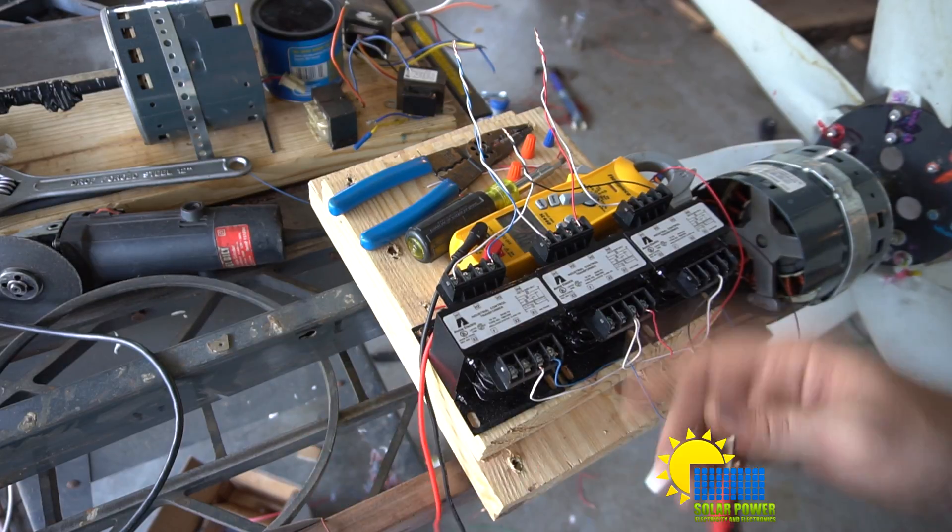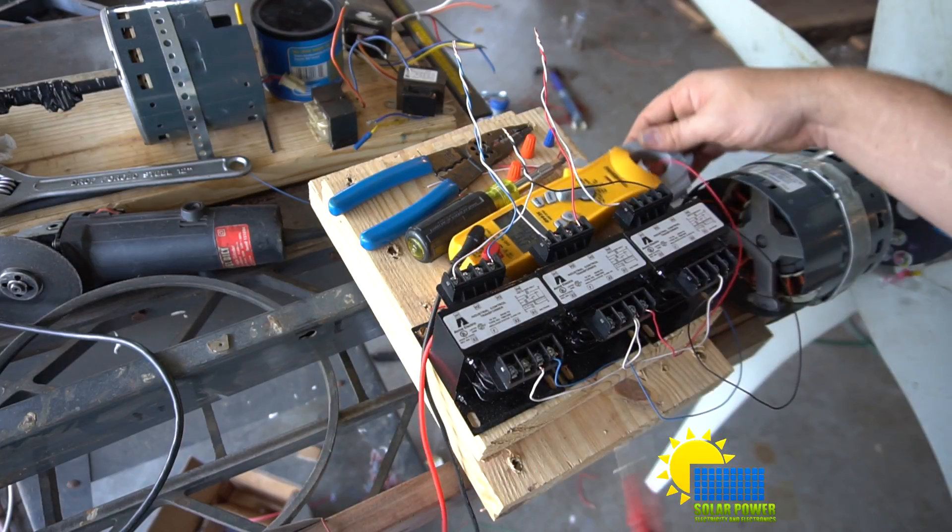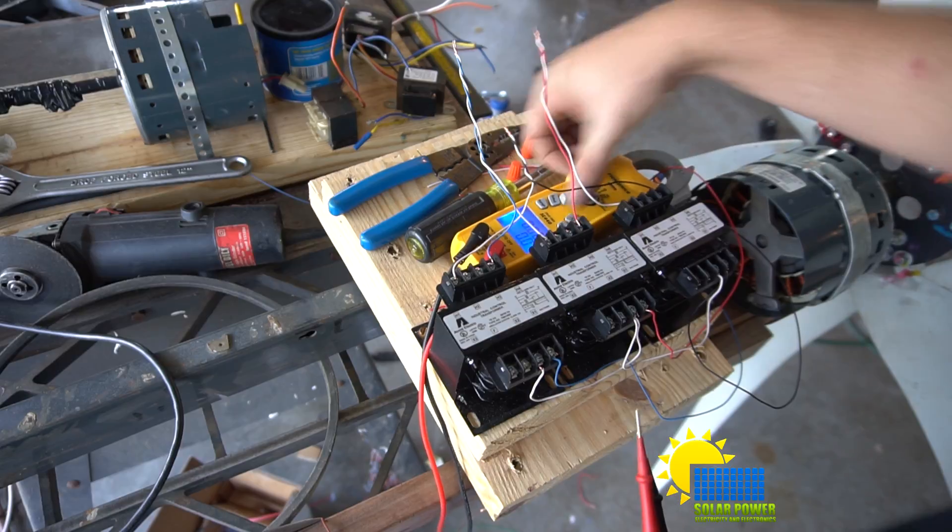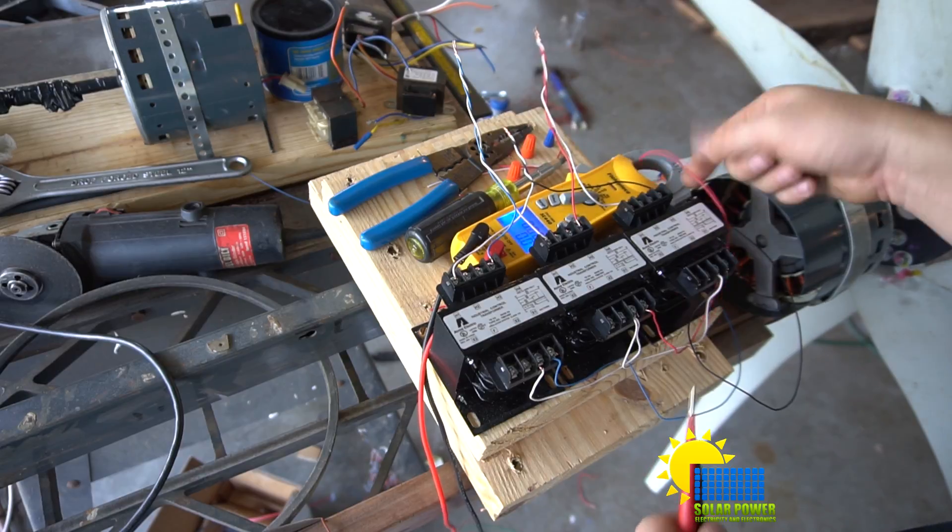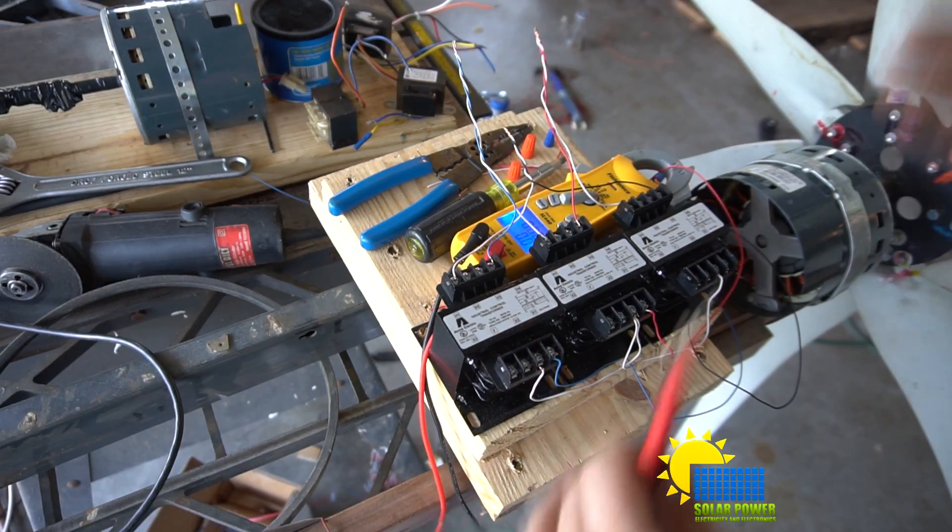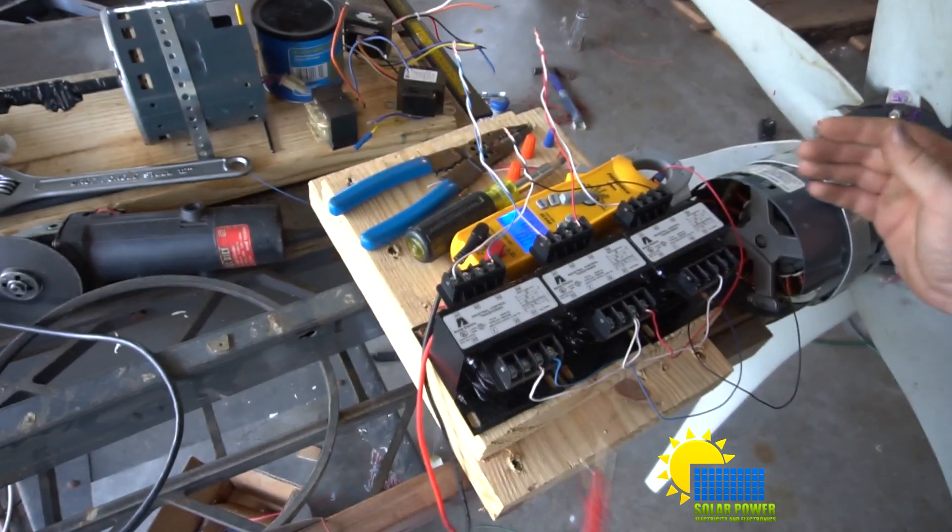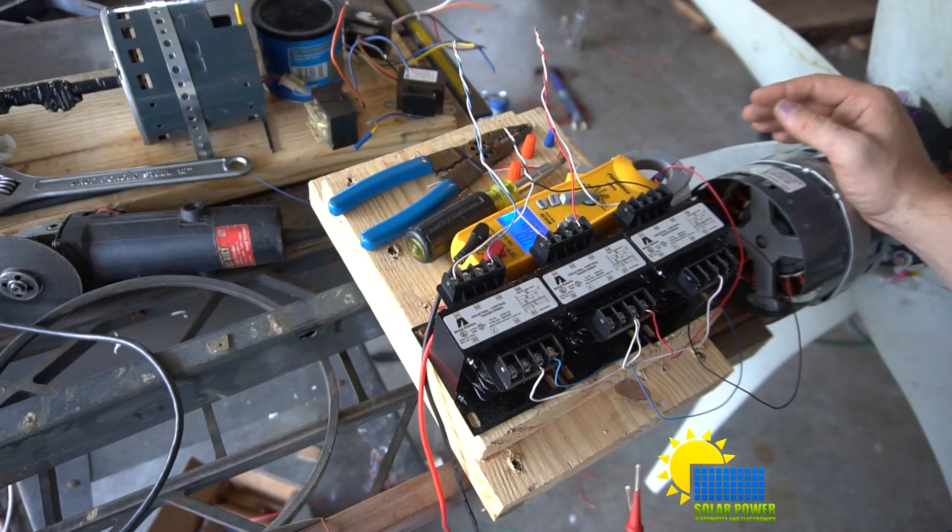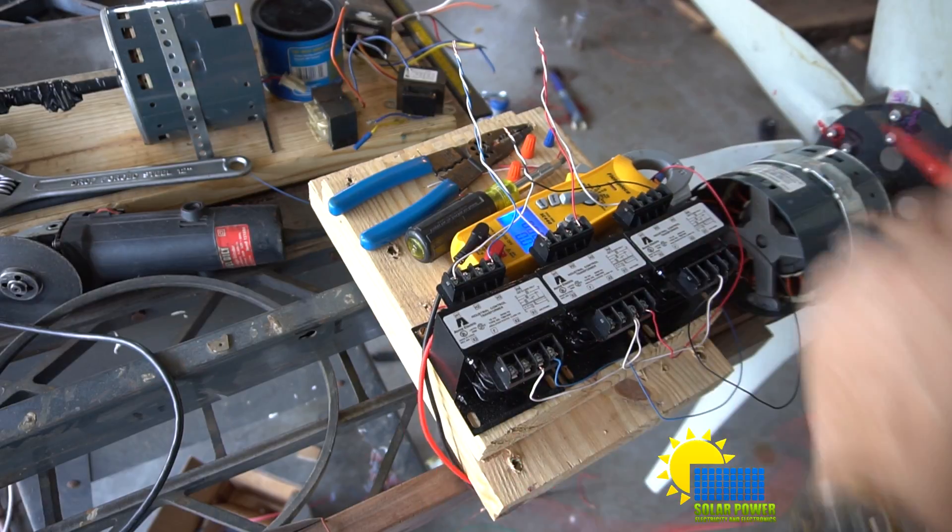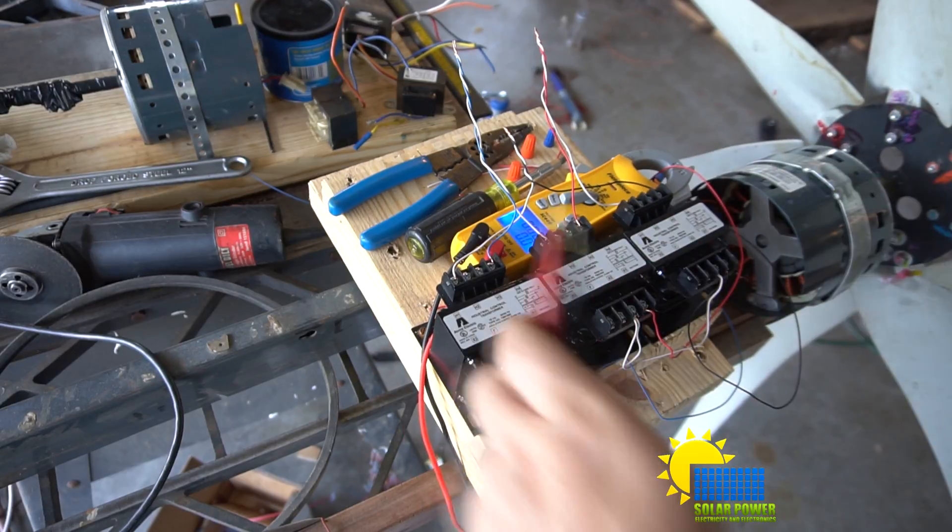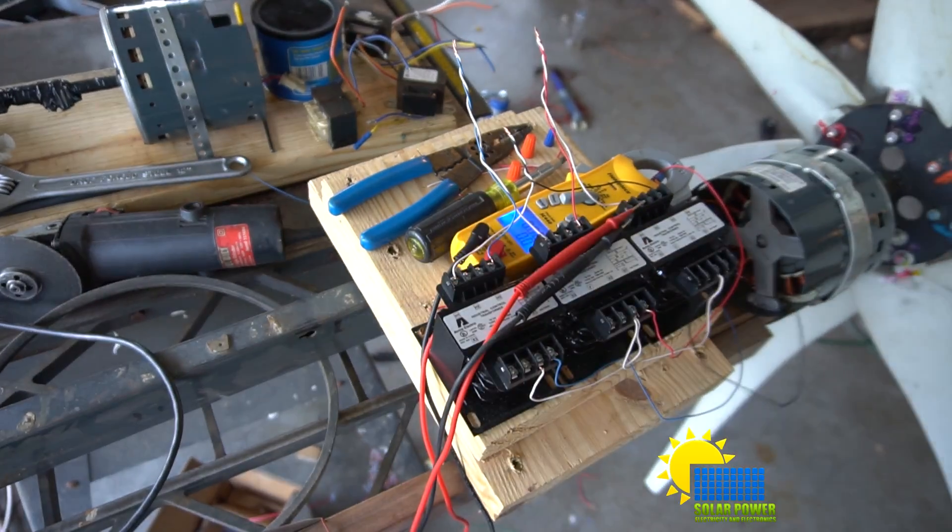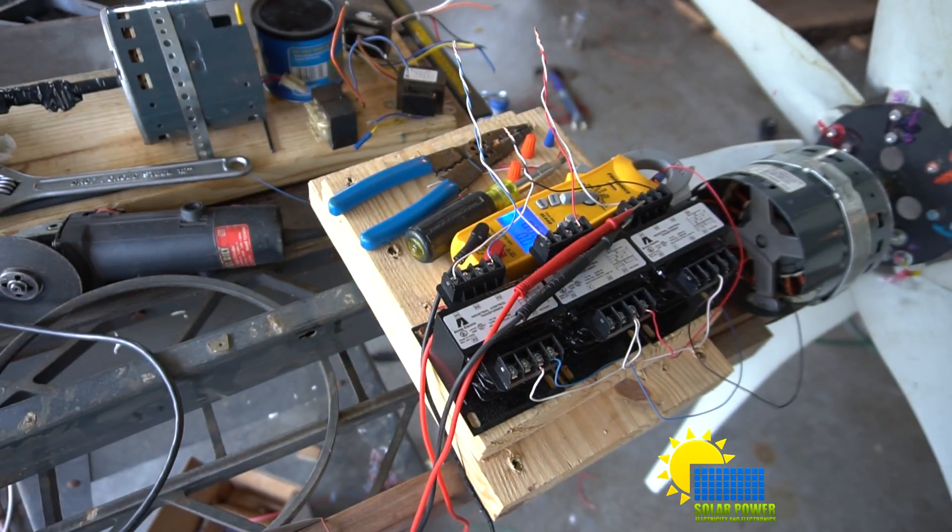For instance, I'm going to go ahead and test. We have our current meter right here on one of the wires, and you have to multiply this by the square root of three. And then I'm going to test by turning the fan on and showing you how this is going to work. It's going to be a little bit louder, so I apologize.